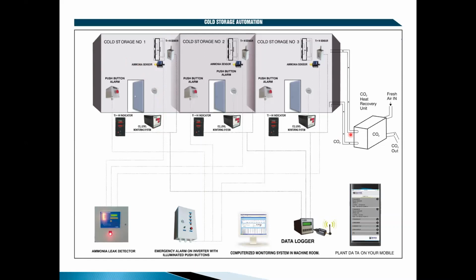We have a CO2 heat recovery system shown over here. Whenever you are taking in fresh air and throwing the cold air out through a heat exchanger, you can pre-chill the fresh air coming in. So this is typically 4 degrees. It will go out at around 25, and this 35 degree air will come in at around 18 to 20 degrees centigrade, which saves load on the evaporator.